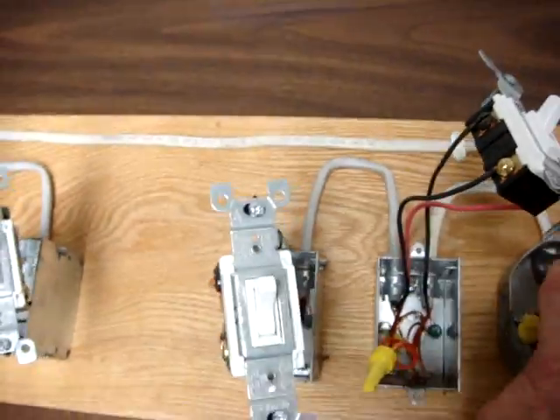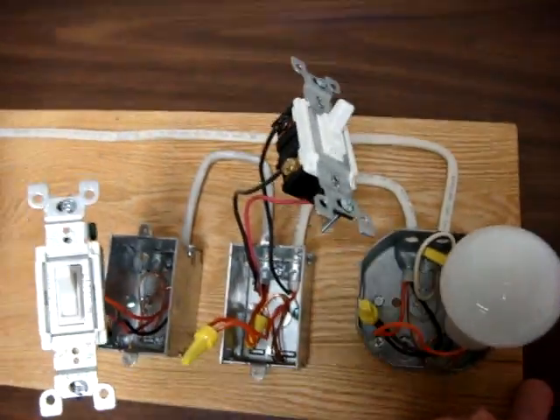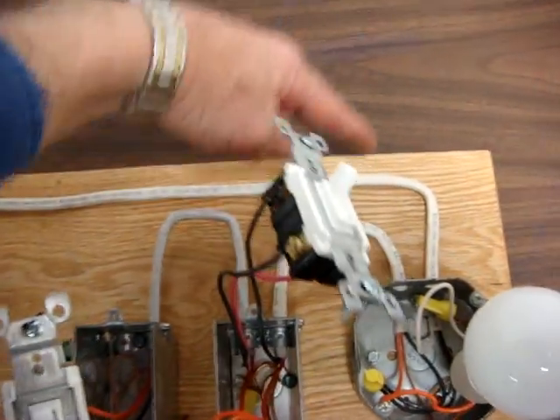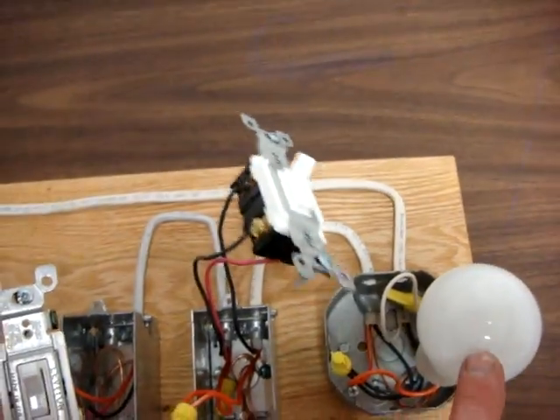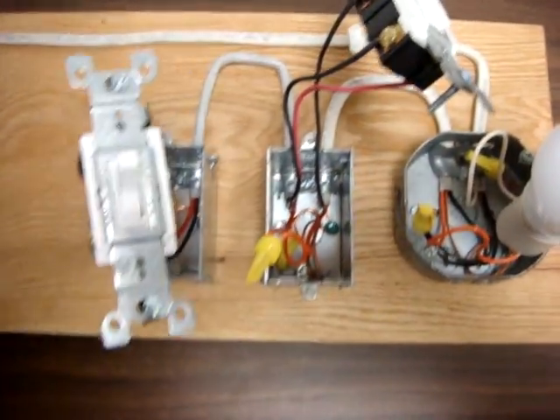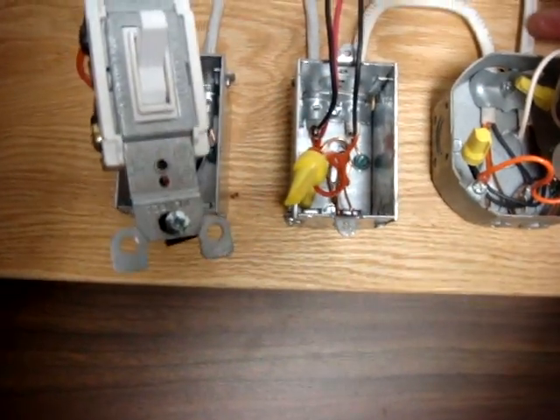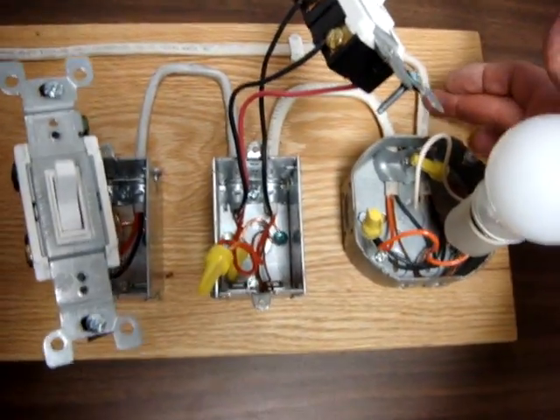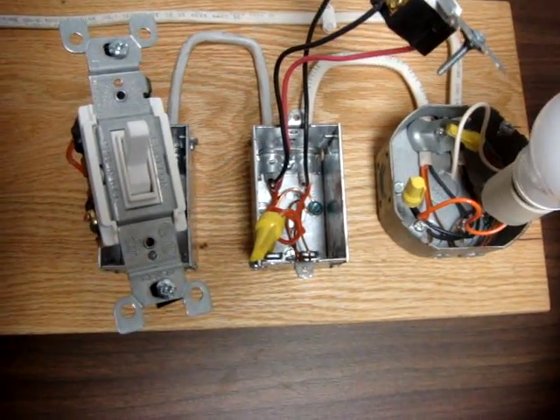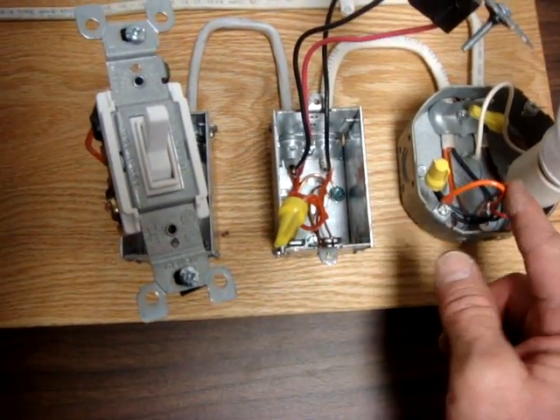In this particular case, this happens to be the power coming in to the light, and then from the light to the other two switches. And in this particular case, the white wire that comes in from the power source just goes to the light fixture, and from the light fixture, the white wire is re-identified as orange.